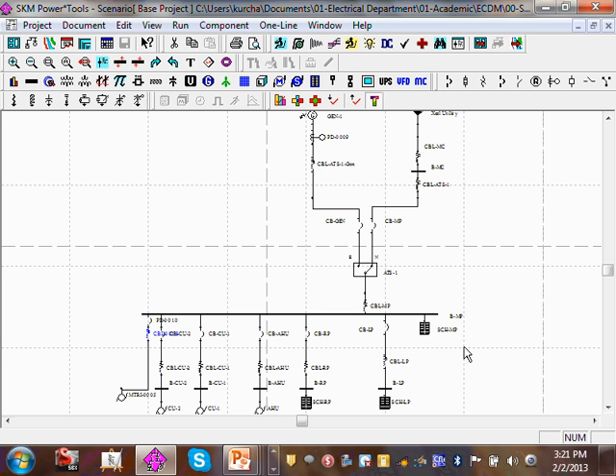If you're in this, really not a whole lot. I did wastewater treatment plants, and I remember after you do a few of them, you're typically dealing with an 800 amp MCC service or a 1600 amp MCC service. Really, most of them are the same. And then I used to ask the wastewater treatment plants, before I even know what the material is, tell me how many aerators you guys have, how many clarifiers. It's not even a load. Give me the aerators. From the aerators, I can give you a size, because you do it so many times and you accumulate the knowledge. But you have to do it a few times before. But then you do the details so you can kind of cover your butt.